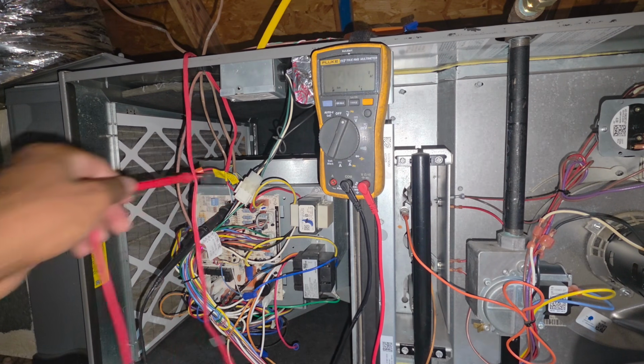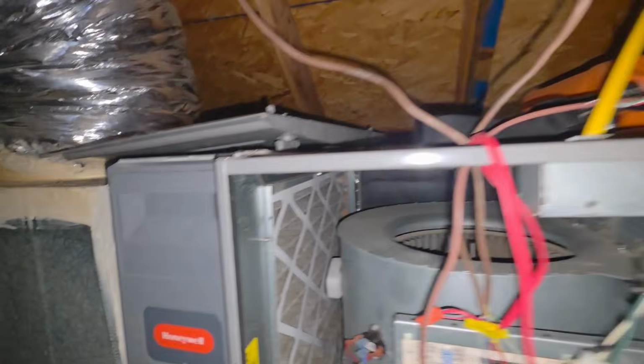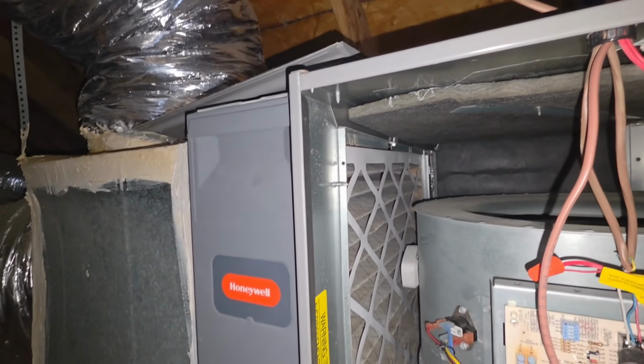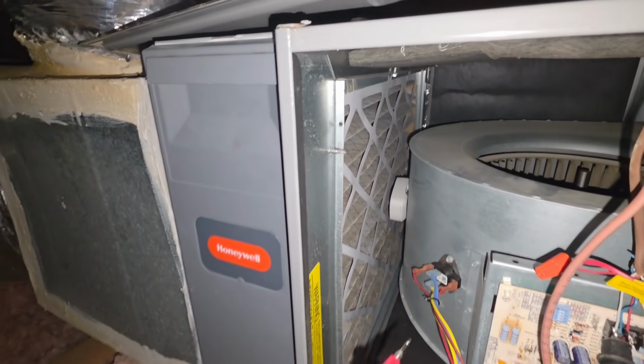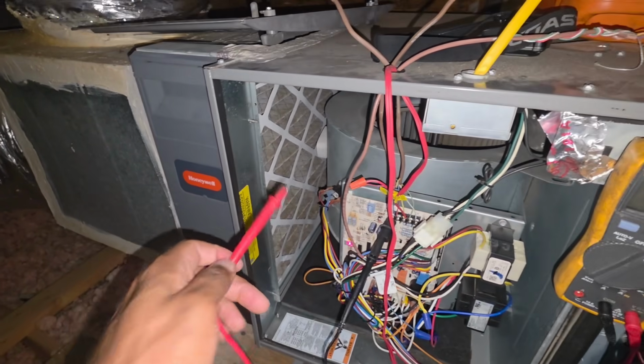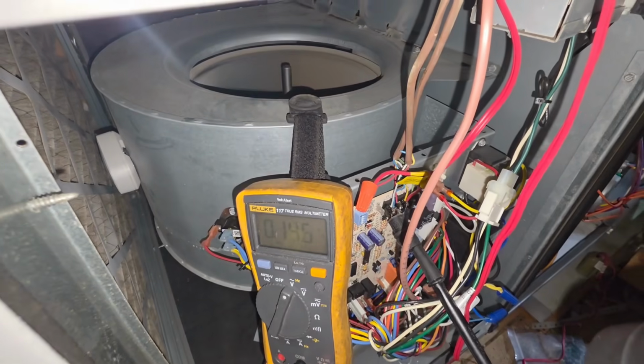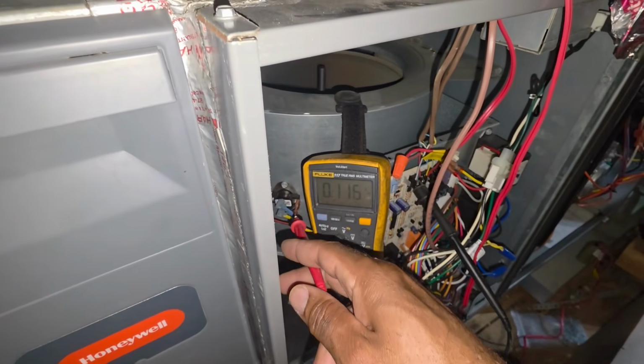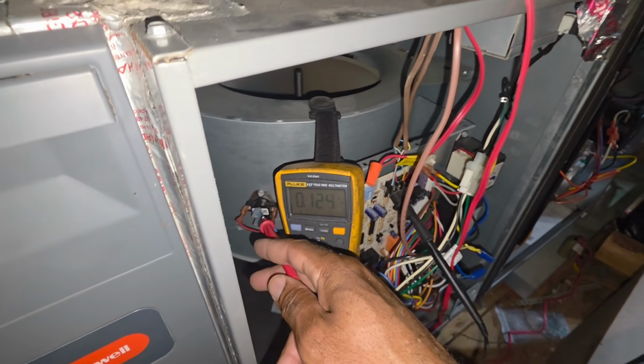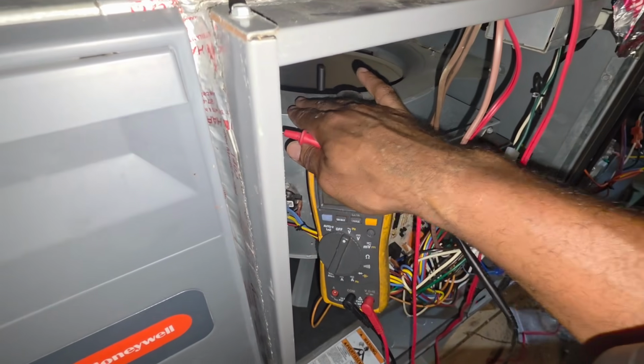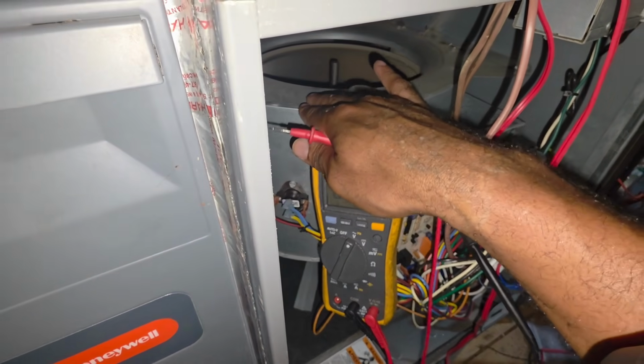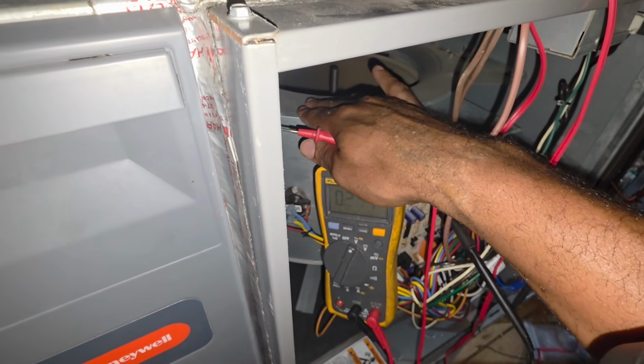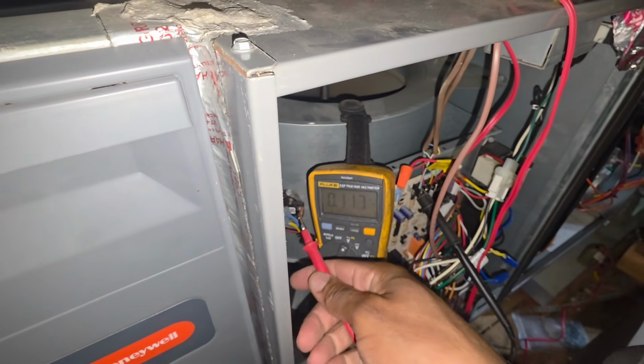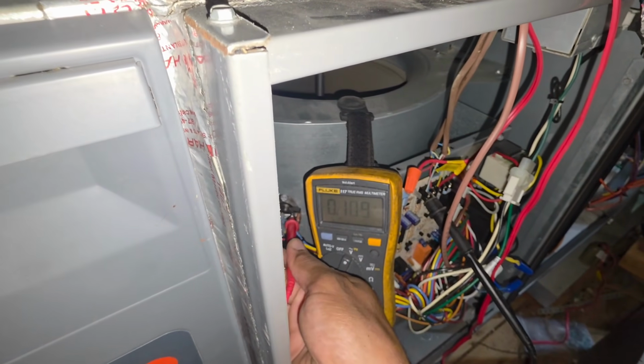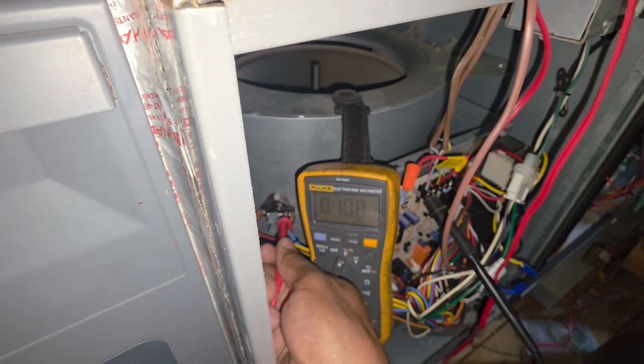Remember all the limits? This is a limit switch right here. I'm trying to show my meter at the same time. All right, so my fan is on. See that limit switch for my fan? It should be closed because my fan is running. The limit switch is connected to this blower assembly right here. And it feels cool to touch to me, so it should be closed. Very important to know when your limits open and close also.